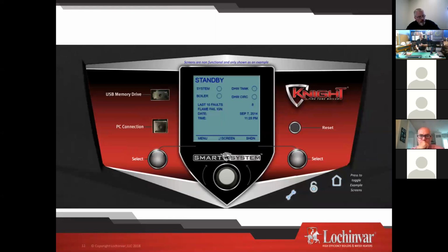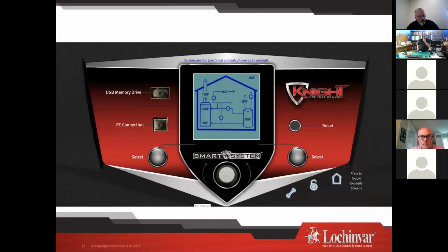All right. I want to look at the last 10 faults. It's going to take me right here. Then I'll actually use the button to move in between. I'll press that scroll knob in, and that'll cycle me through when the faults were. And this screen right here is probably my favorite addition to the 3rd generation of the control. I see every sensor and every temperature. And if the boiler were actually firing in this picture, it would show you the firing rate. This is a great way to take a look and say, hey, what's going on at this moment in time in the boiler?